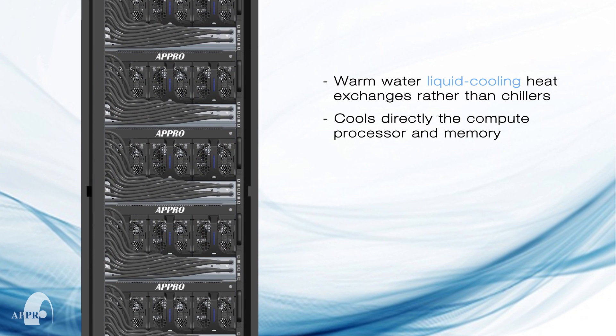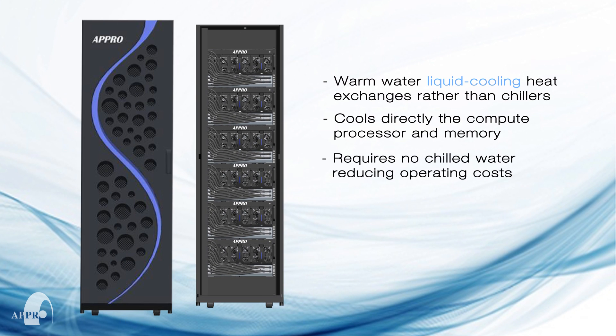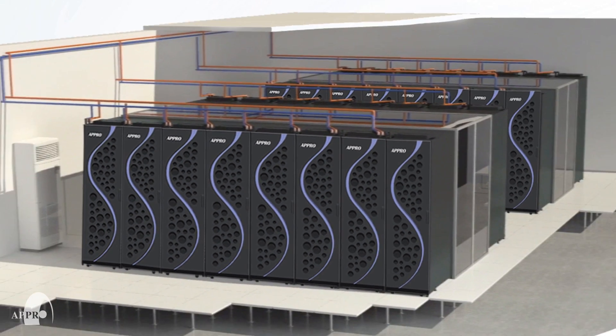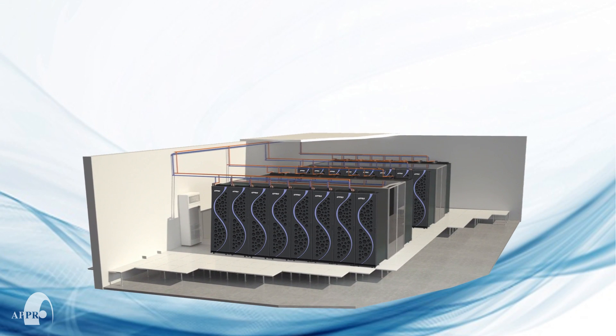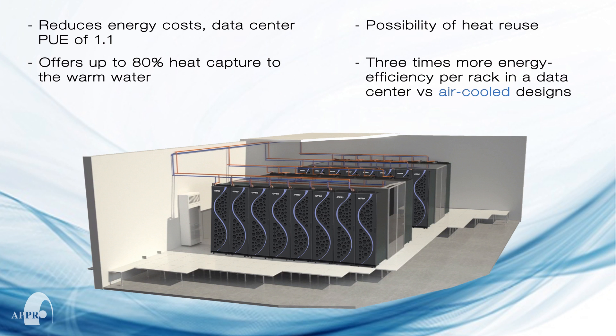It offers a superior energy efficient design using warm water liquid cooling heat exchangers with no chillers. The system uses less energy and offers lower TCO and faster ROI by requiring fewer or no air conditioning units in the data center. The APPRO ExtremeCool supercomputer can reduce typical energy consumption while yielding a data center PUE of 1.1. It also produces 80% heat capture to the warm water for possible heat reuse, and delivers three times more energy efficiency per rack versus traditional air cool designs.